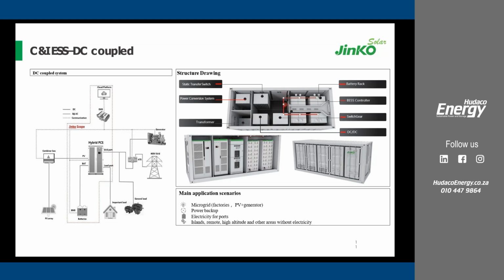So when we talk about generator, it could also mean grid, right? Yes, could be grid as well. For diesel generator integration and the diesel saver option, what communication is there between the generator and the PCS in terms of limiting feedback to the generator? Because the generator will always need to supply a certain amount of power, and there must be something regulating that in the PCS, right?